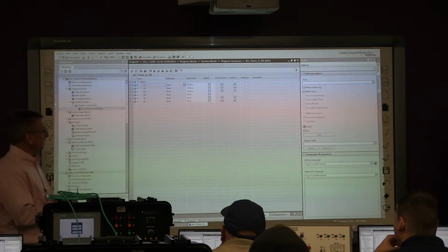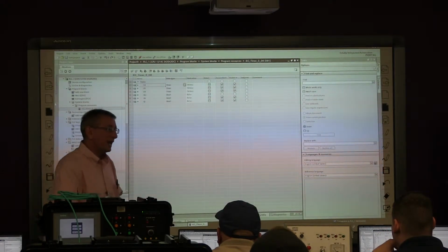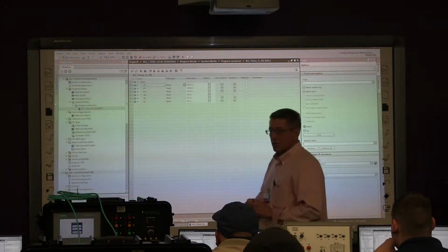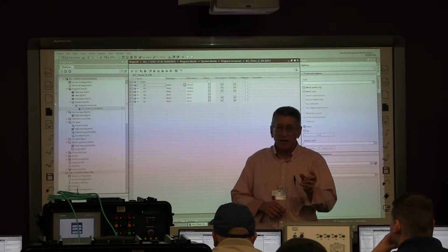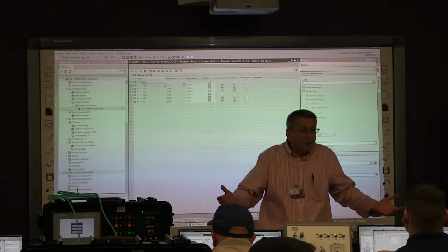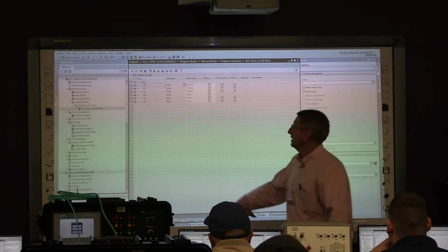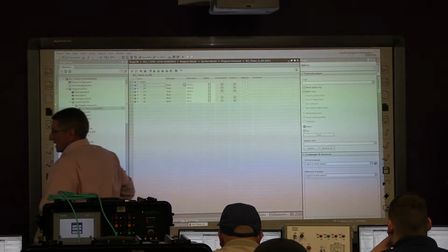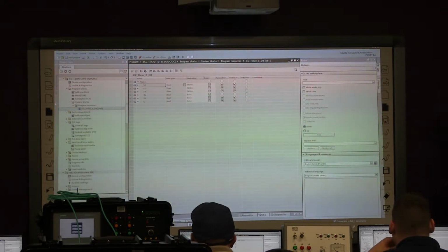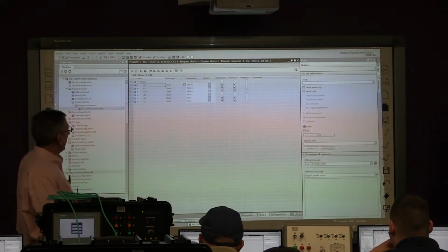And I'll tell you what the difference is here in just a minute. The ET is the elapsed time. What's the elapsed time? How long? The accumulated value. The start time is if you want to start this timer at some other time rather than 0. Doesn't make sense why you would want to use that, but it's there, right? So you can start it, if it's set for 10 seconds, we can start it at 5 seconds if we want. Cut your production time in half. There you go. Yeah.